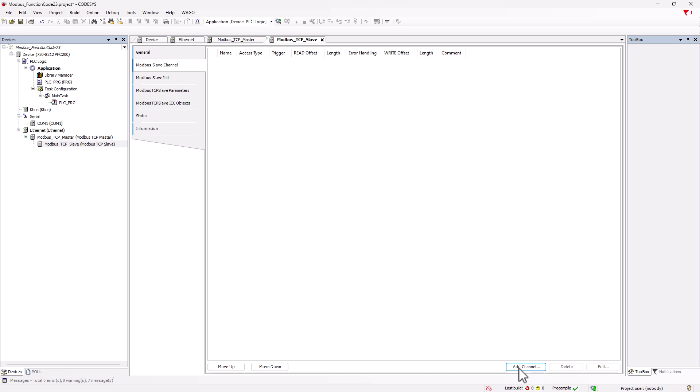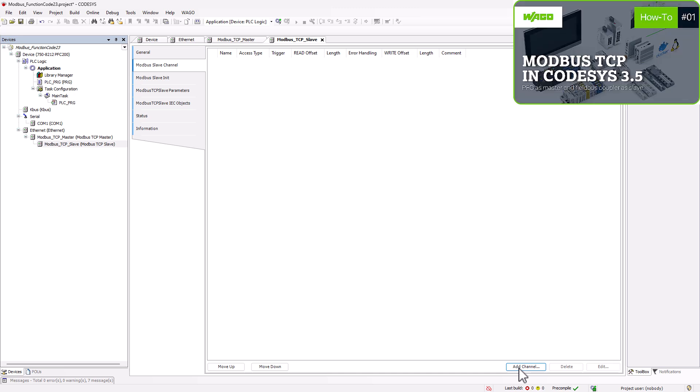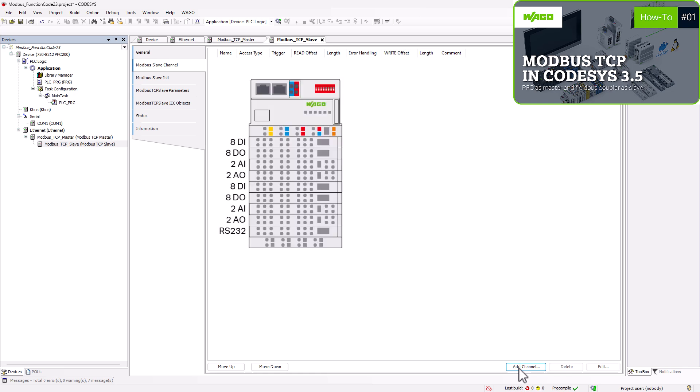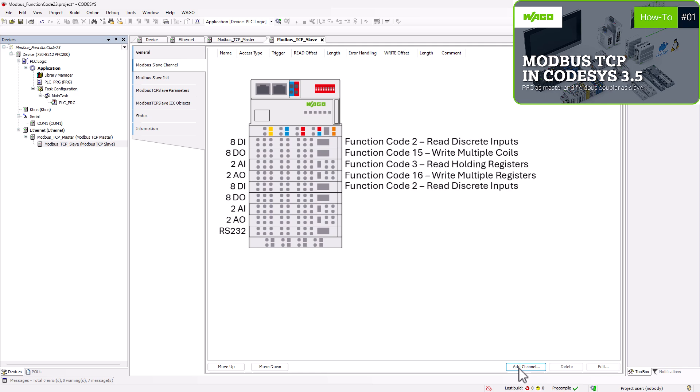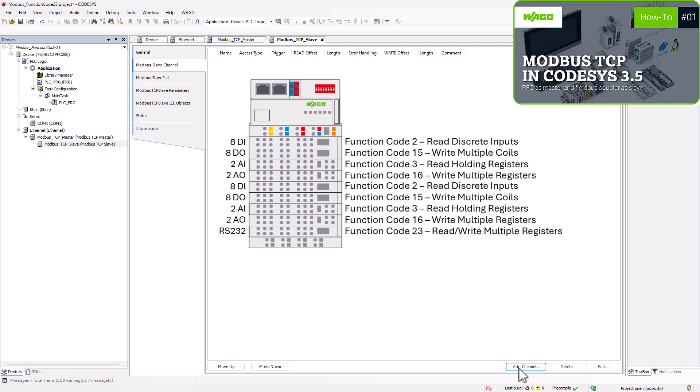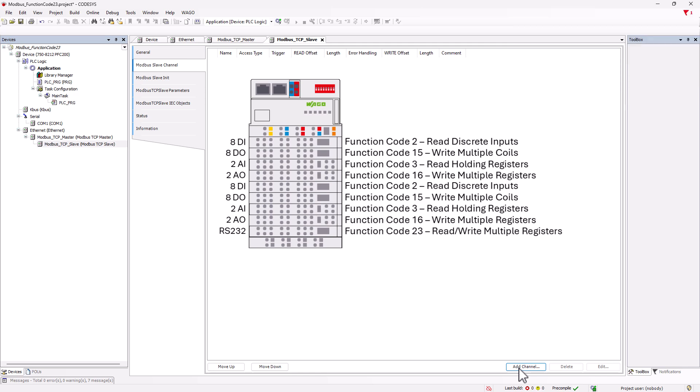In the Modbus basics tutorial, Modbus TCP in CodeSys 3.5, PFC as master and Fieldbus Coupler as slave, we showed the possibility of creating a separate Modbus channel for each module. For small systems, this is an easy and clear method, but with each additional channel the bus load increases, which can lead to performance problems in larger systems.